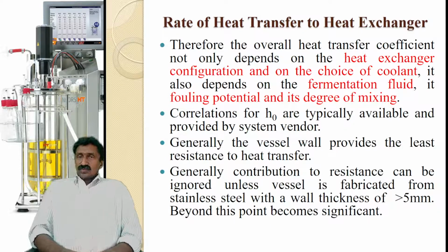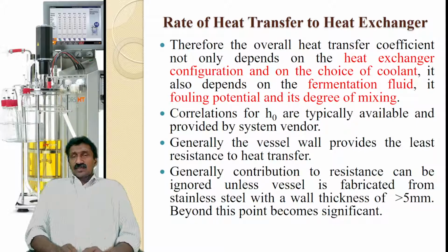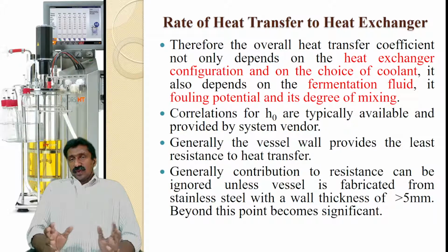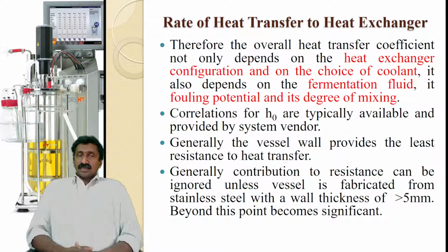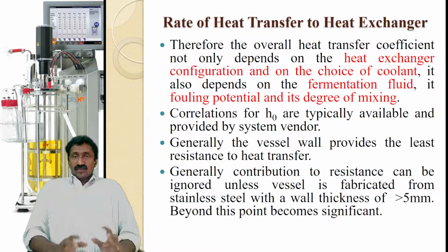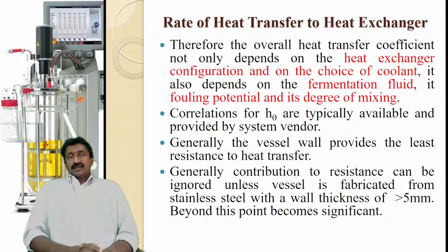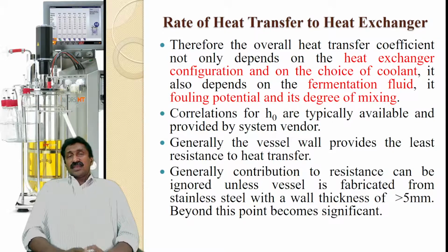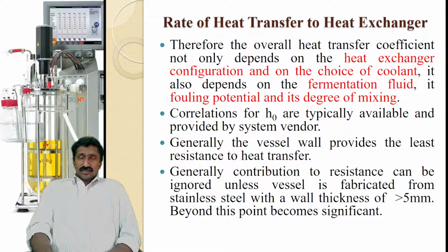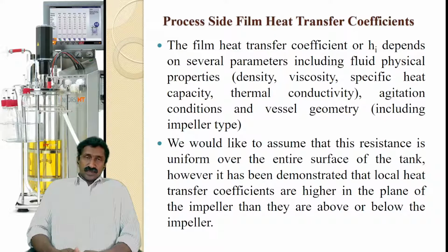Generally, the vessel wall provides the least resistance to heat transfer. Generally, its contribution to resistance can be ignored unless the vessel is fabricated from stainless steel with a wall thickness of greater than 5 mm. Beyond this point, it becomes significant. So if the wall thickness of the vessel is not greater than 5 mm, then that is not significant. But if your vessel wall thickness is more than 5 mm, then that becomes significant because it may affect the overall heat transfer efficiency. So these are some general concepts.